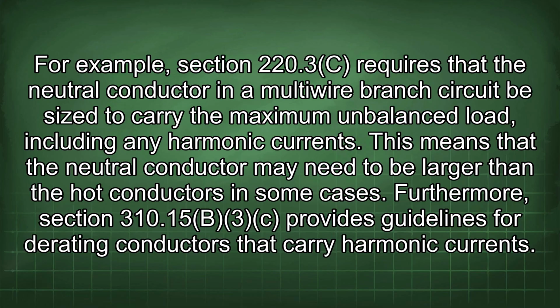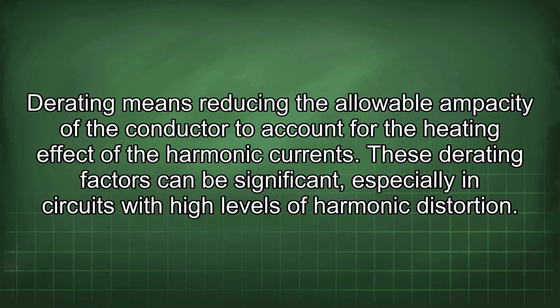Furthermore, section 310.15b3 provides guidelines for derating conductors that carry harmonic currents. Derating means reducing the allowable ampacity of the conductor to account for the heating effect of the harmonic currents. These derating factors can be significant, especially in circuits with high levels of harmonic distortion.